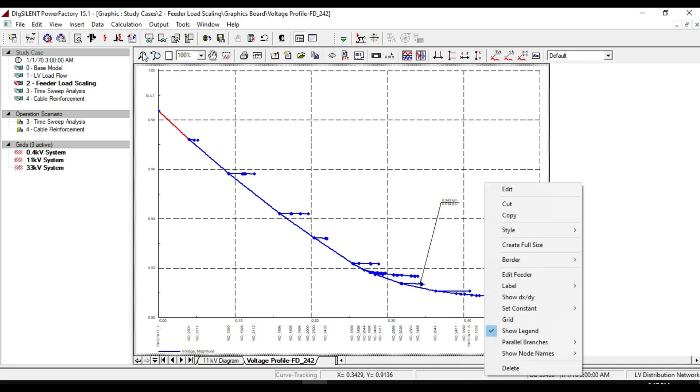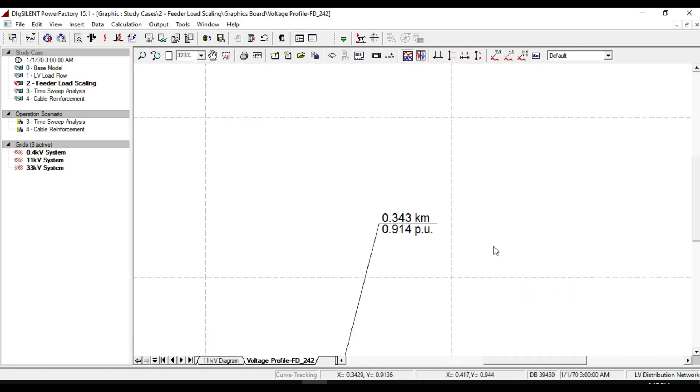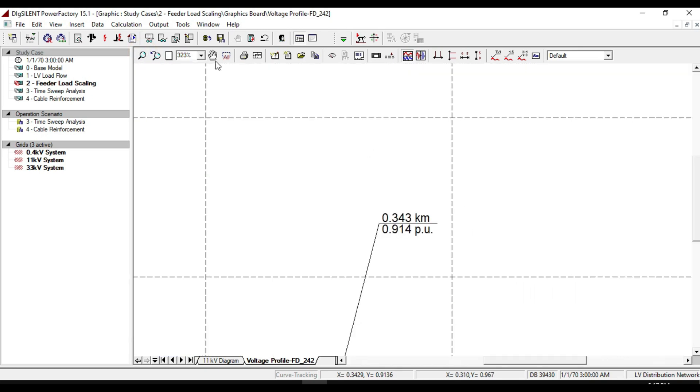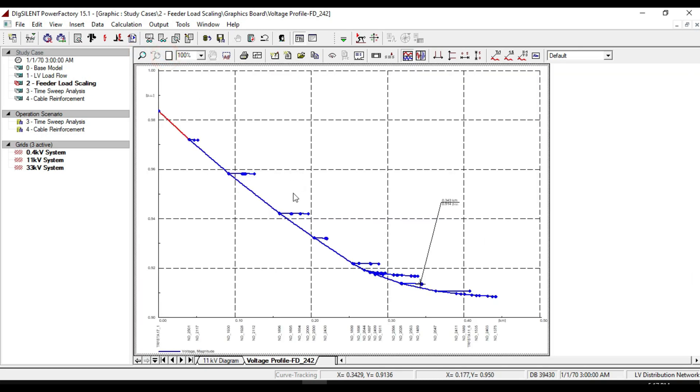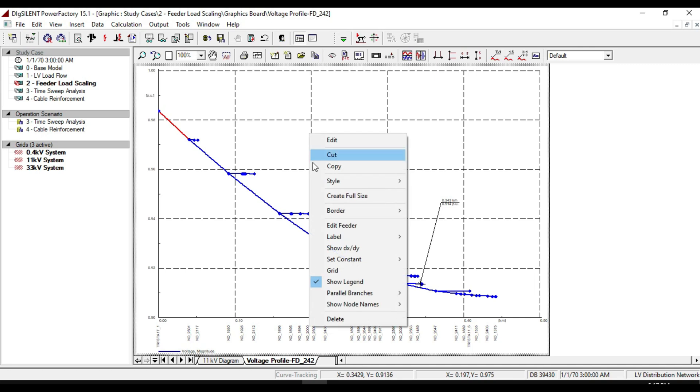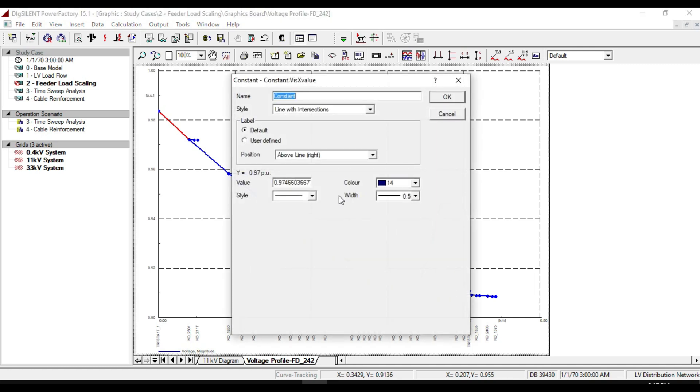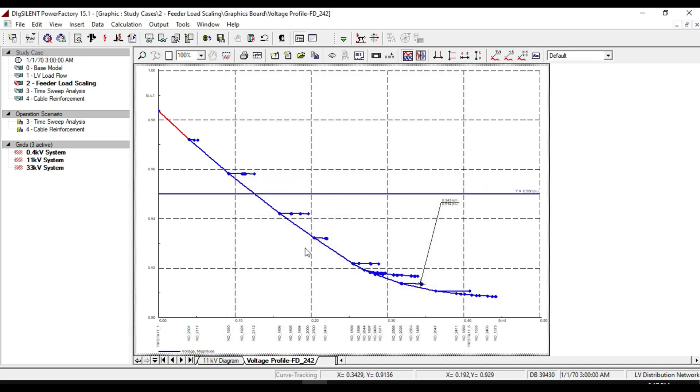We can also create a certain threshold to the curve. Right-click, from the Set Constant select Y value and set the value to 0.95. As you can see, many of the loads in this feeder have a voltage below 95%.